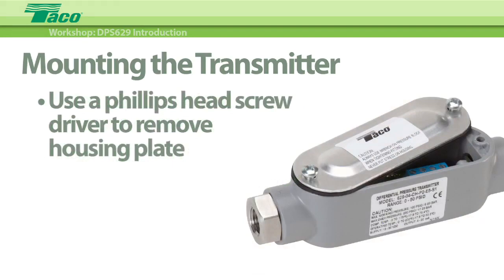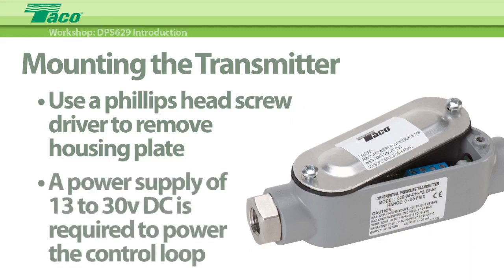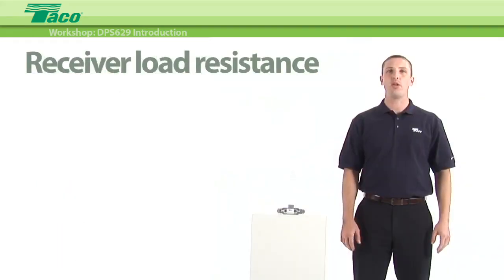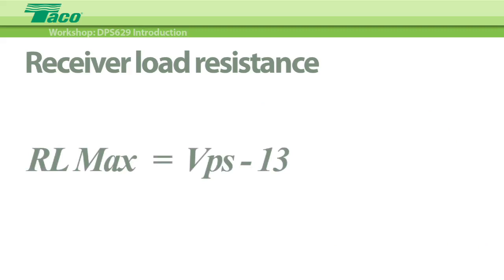Next, open the housing by using a Phillips head screwdriver to remove the screws that anchor the plate in the center of the housing. An external power supply delivering 13 to 30 volts DC with minimum current capability of 40 milliamps DC per transmitter is required to power the control loop. The range of the appropriate receiver load resistance for the DC power supply voltage available is expressed by the following formula, where RL, the receiver load resistance, is equal to the voltage of the power supply minus 13, divided by 20 milliamps DC.